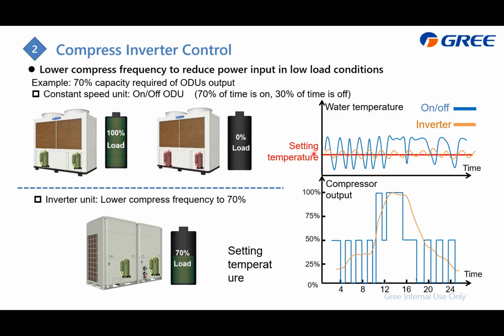And here is the comparison between the on-off at the upper side and the inverter. For the inverter, that means we can change the compressor RPM to meet the load. And here is an example. If we only require 70% of the load, then the on-off just needs to turn on and off over time: 70% on and 30% off. And for the inverter, we can adjust the compressor RPM exactly to 70% to meet the load.